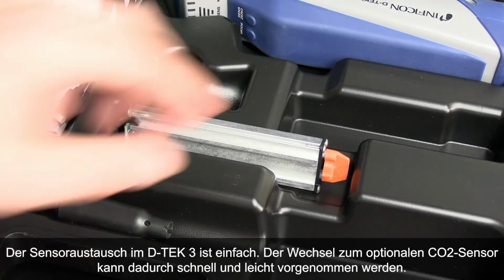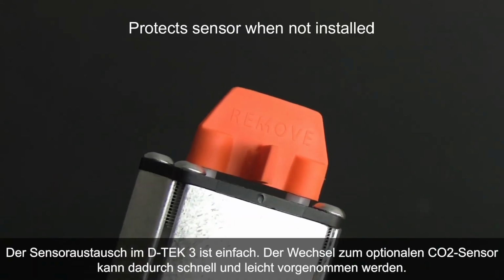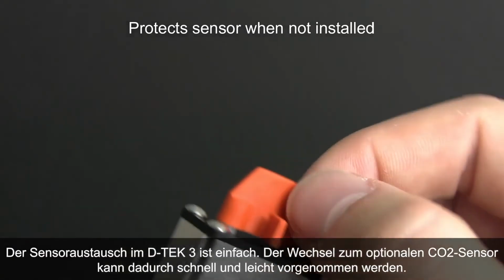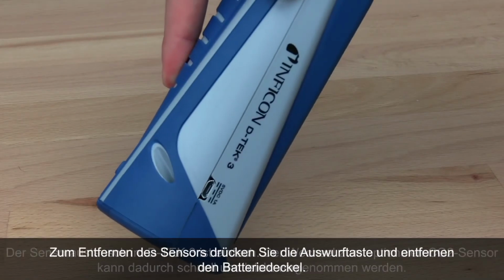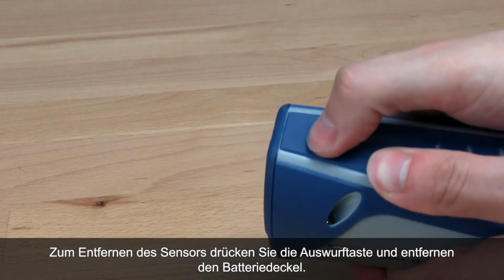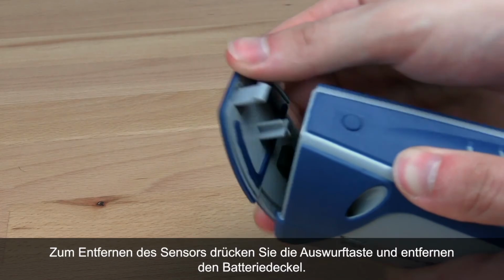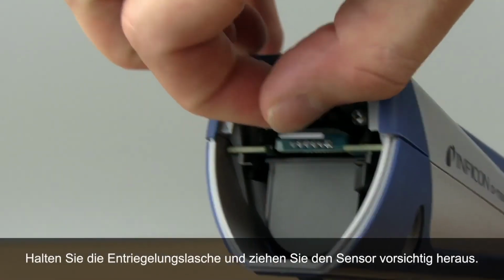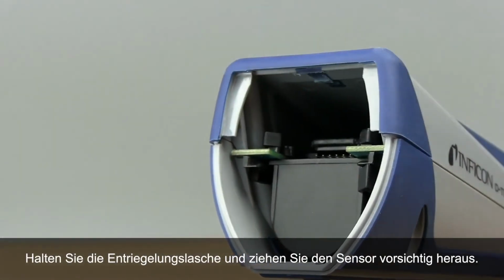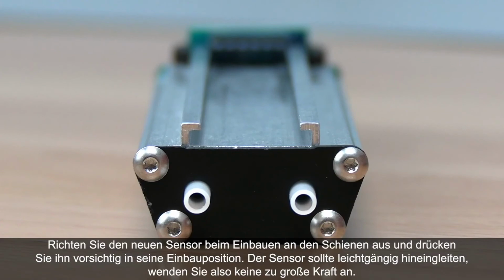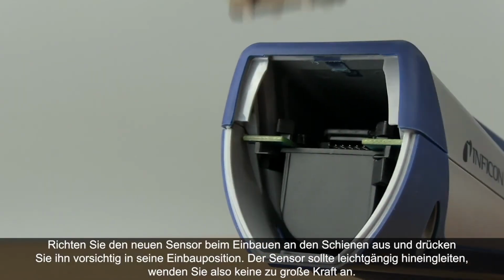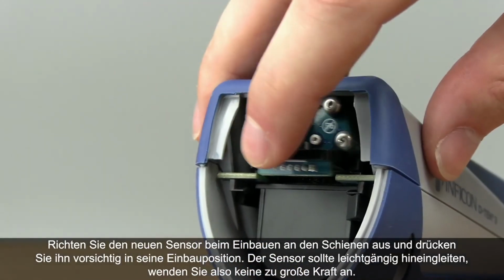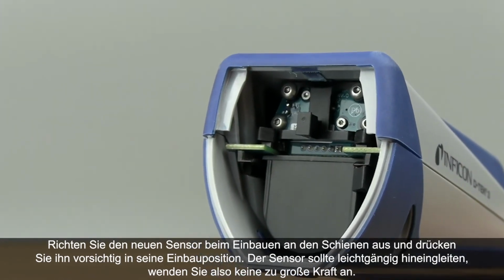Changing sensors with D-TEK-3 is simple. This makes switching to the optional CO2 sensor quick and easy. To remove the sensor, press the eject button and remove the battery door. Hold the sensor release tab and gently pull the sensor out. To install the new sensor, line the sensor up with the rails and gently push the sensor into place. It should slide easily, so don't force it.